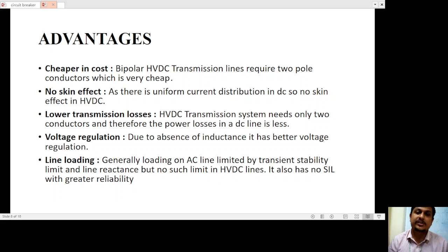Lower transmission losses, because in a DC system only two conductors are needed, but in case of AC there are three conductors needed. Voltage regulation is better because inductance is not present in the DC system; only one parameter is present, that is resistance, with no inductance or capacitance. Due to the absence of inductance it has better voltage regulation. Line loading: generally loading of an AC line is limited by transient stability, but there is no such limit in HVDC. So it also goes in favor of HVDC.